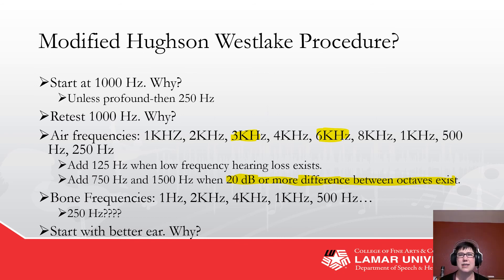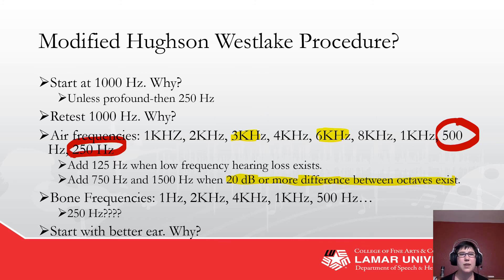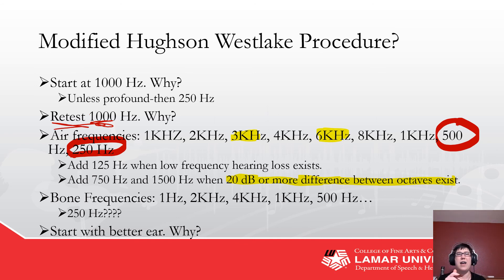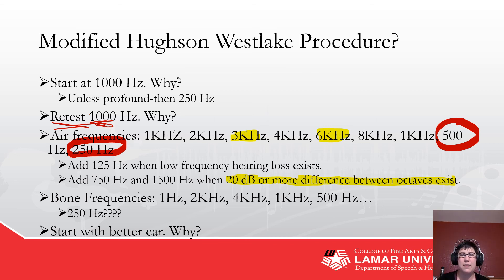Some people do 500 and 250 differently. Textbook says after you retest 1,000 Hz to do 500 then 250. Another thing I highly recommend, especially if you're going to be fitting hearing aids: if there's any low frequency hearing at all, add 125 Hz because that's an important one for occlusion effect, patient comfort, and noise experience.